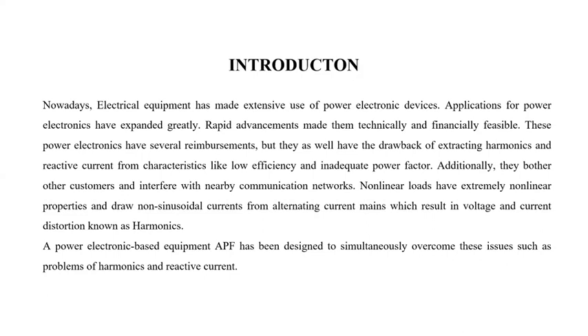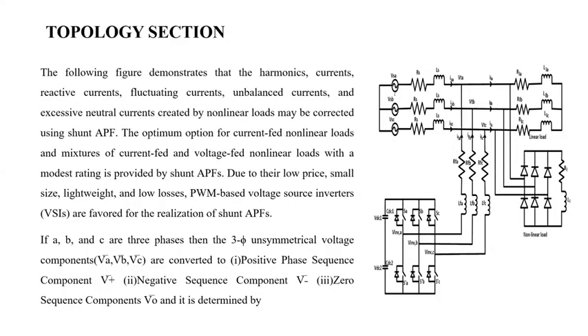Non-linear loads have extremely non-linear properties and draw non-sinusoidal currents from alternating current mains, which results in voltage and current distortions known as harmonics. A power electronics based equipment, the active power filter, has been designed to simultaneously overcome these issues, such as problems of harmonics and reactive current. Coming to the topology section, the following figure demonstrates that harmonics, reactive currents, fluctuating currents, unbalanced currents and excessive neutral currents created by non-linear loads may be corrected using a shunt active power filter.